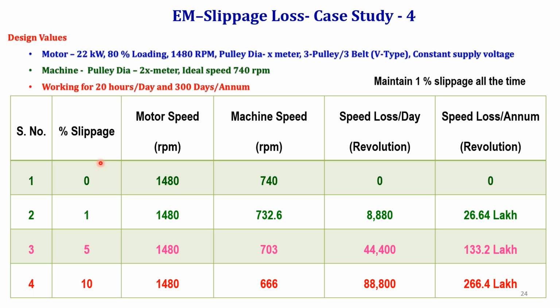Most of the time, slippage losses are not addressed, but some industries regularly measure them at regular intervals. Even some top companies measure the slippage losses for the motor connected to the machine with a belt and pulley arrangement at an interval of 1 week, 10 days or even 15 days. They note the percentage slippage loss, and if it deviates from their set value, they automatically take corrective action. Now this slide will show you a simple example. It's not a case study, it's an example where I'm taking a 22 kilowatt motor at 80% loading condition.